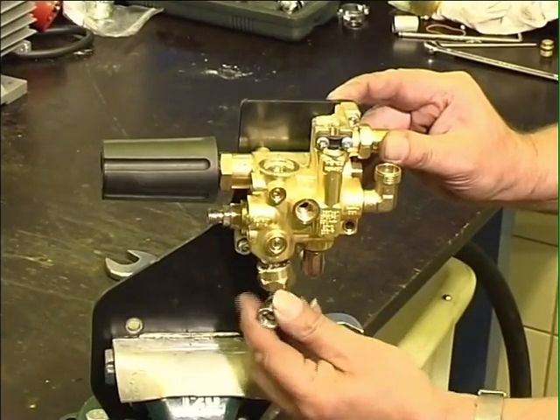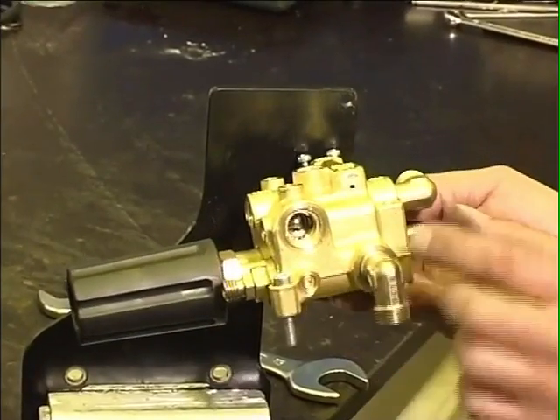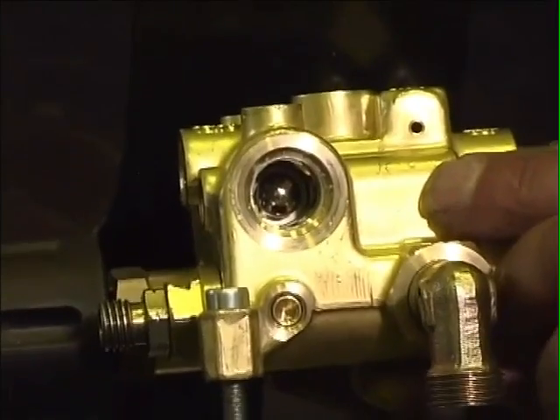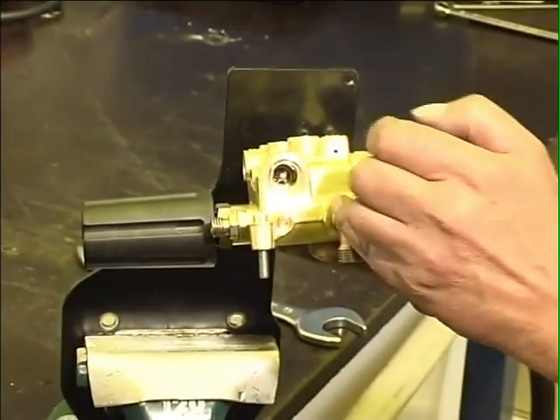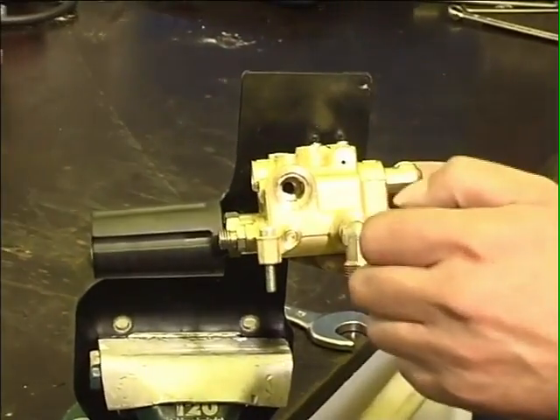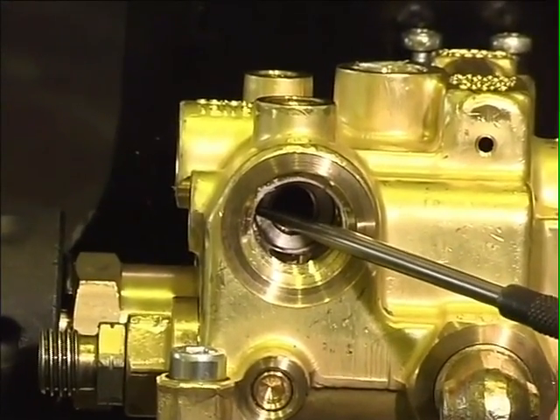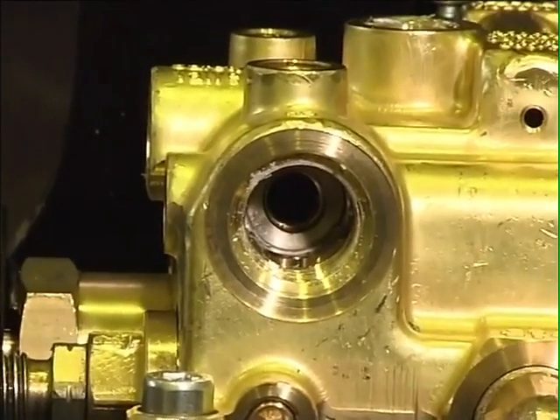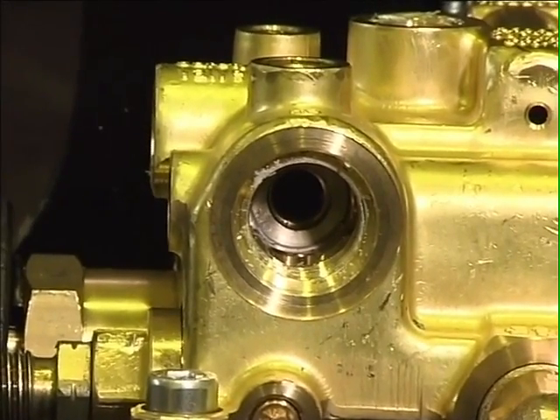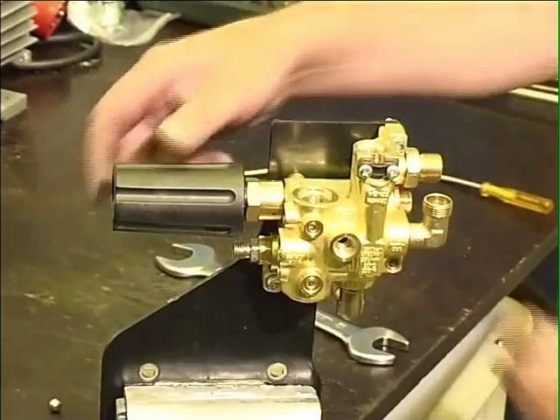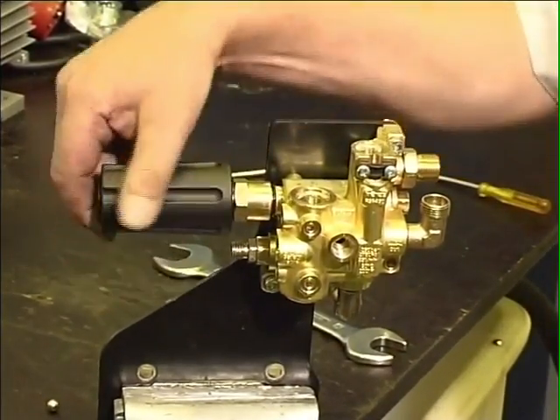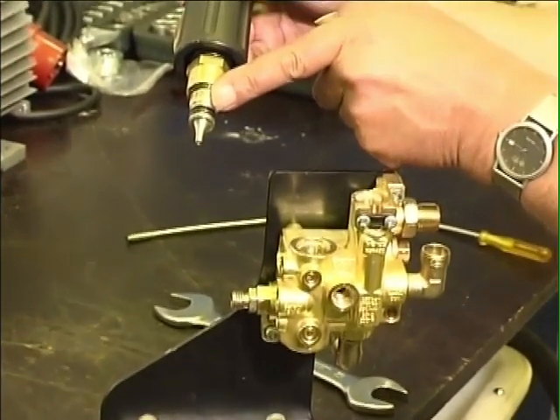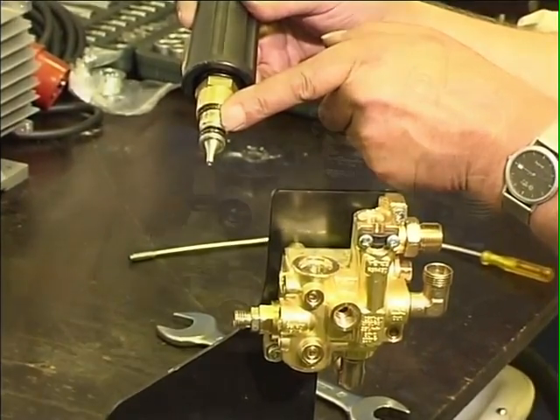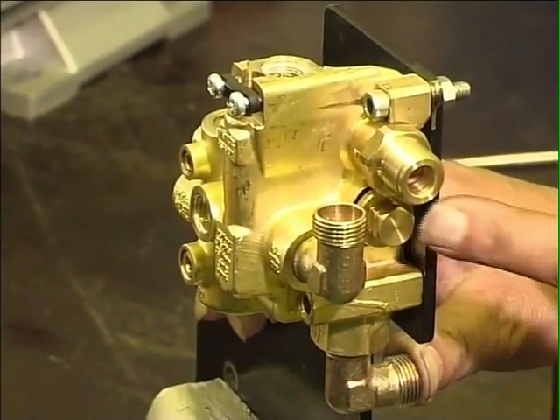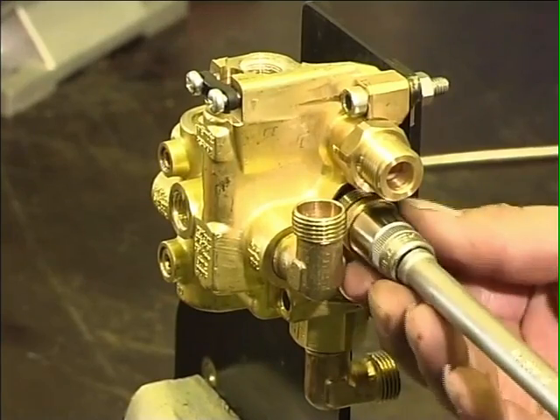After removing the inlet piece, we tilt the safety block for better demonstration. The ball of the bypass for the heating coil safety valve is removed. As shown, seat and stainless steel ring can be replaced, then reassemble everything in the right order. The hand wheel and regulating piston of the unloader are removed. If necessary, seals can be cleaned and replaced. The pressure adjustment of the bypass unloader can be removed with seat, spring and ball. There is an O-ring behind it.